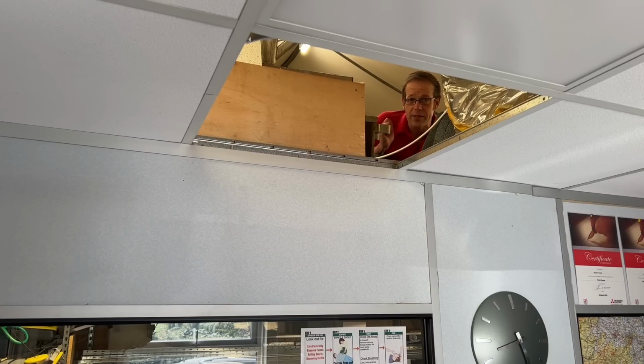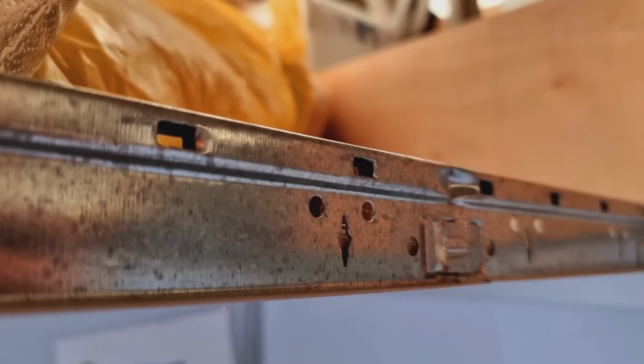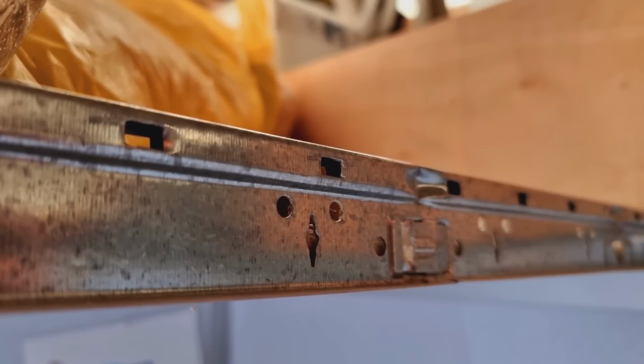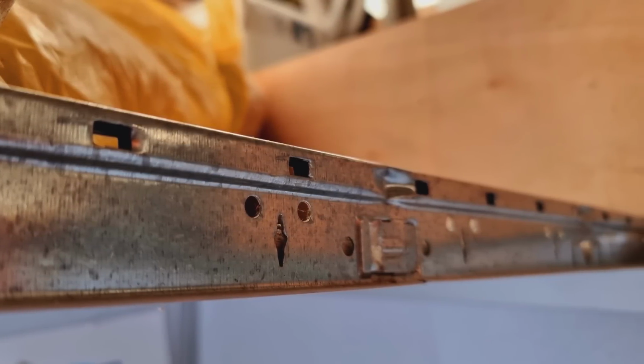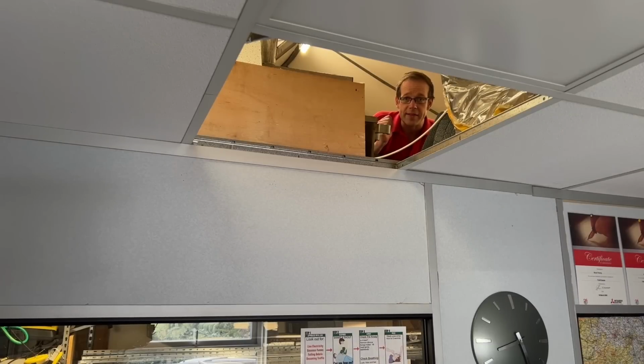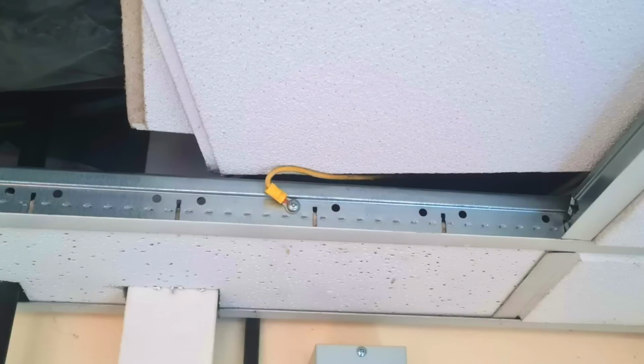So the question now is, does that ceiling grid fall into either of these categories? Well, is it part of the electrical installation? Absolutely not. You may come across installations where the cables have been thrown over the grid and it's seen as some kind of built-in cable support. It should absolutely not be used for this purpose. If cabling has been installed like this, the solution is not to earth the grid, but rather to provide proper support for the cables. So it's not part of the electrical installation, therefore it's not an exposed conductive part, so you wouldn't earth it for this reason.